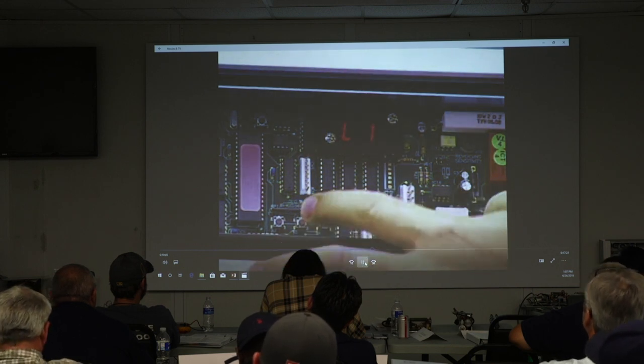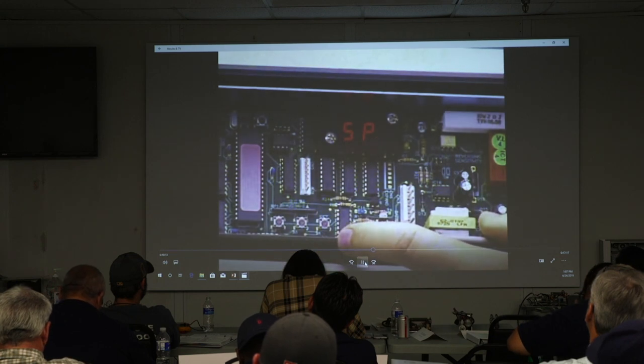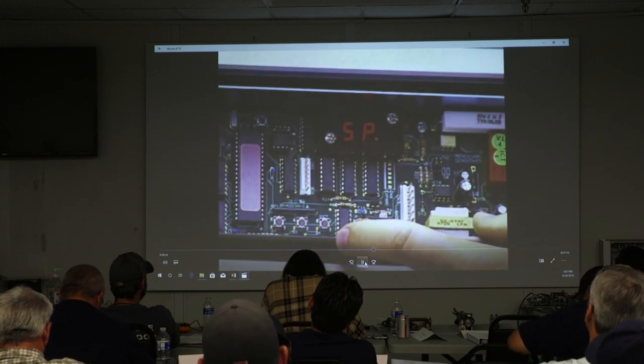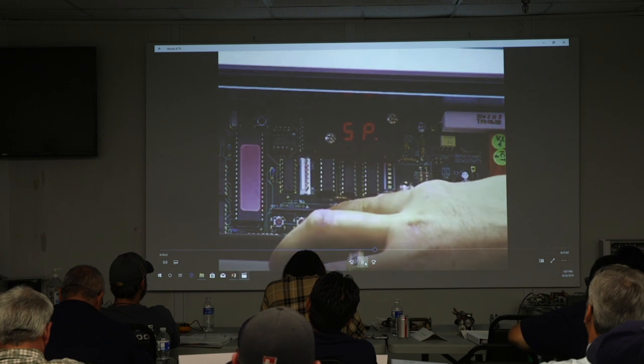Default is off. L1 is the on-off parameter that locks the door whenever the control is in the one-way mode. Default is off. SP is the on-off parameter that is turned on when side light sensors are used. This parameter puts the door in check speed when the side light sensors detect a person in the opening path of the door. Default is off.